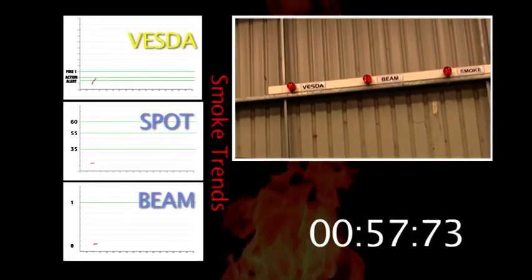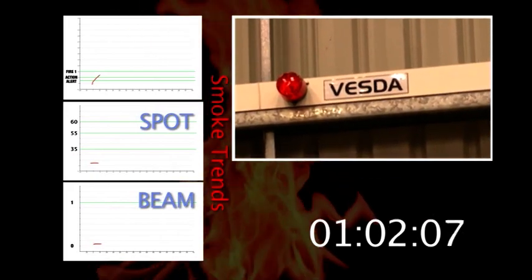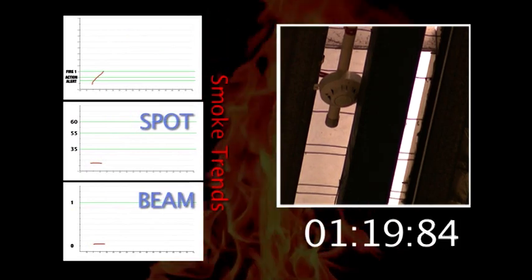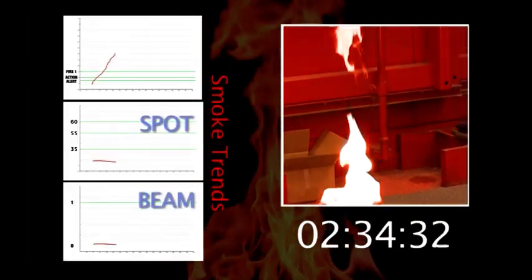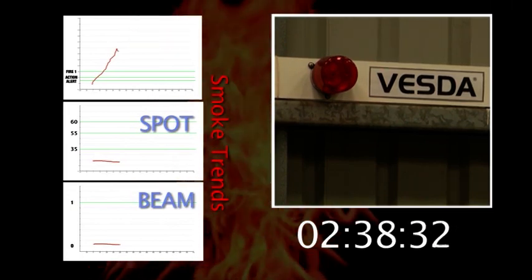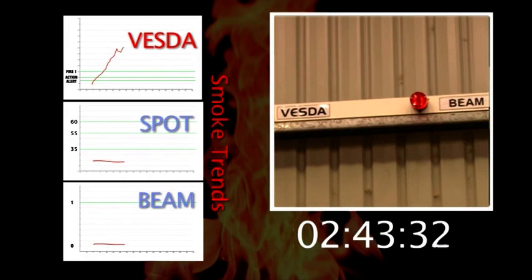In less than sixty seconds, the VESDA has already registered the presence of smoke and triggers the first alert after one minute eighteen seconds. At two minutes thirty-five seconds, the VESDA has triggered fire one alarm, while there is still no indication of smoke from the point or beam detectors.